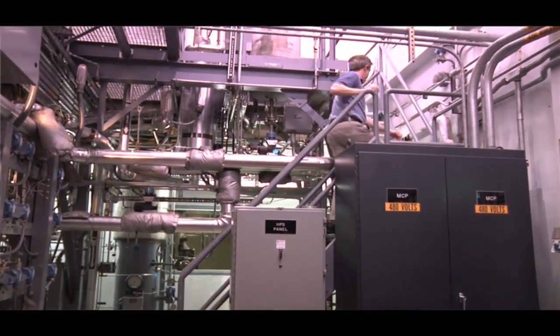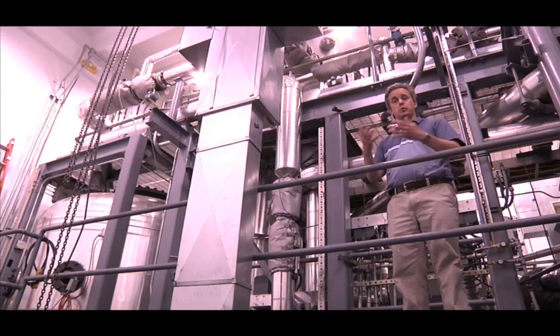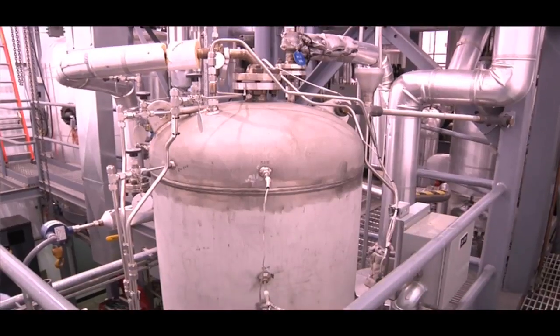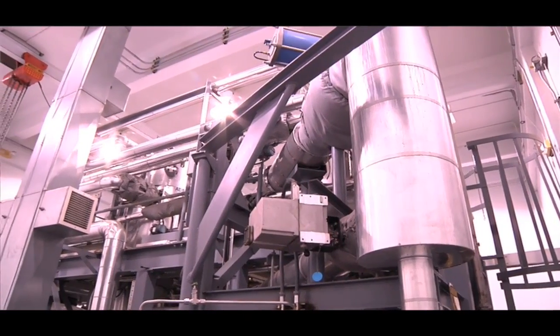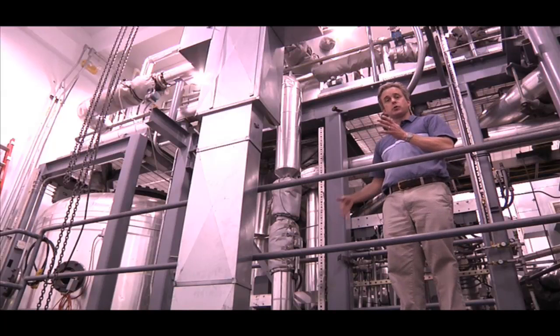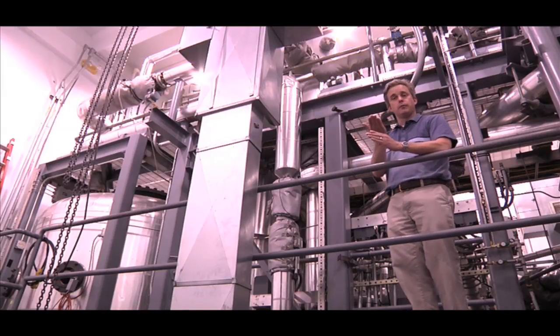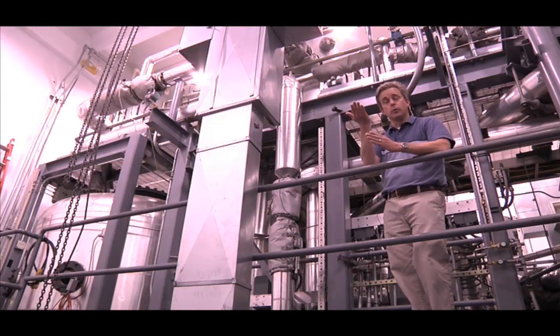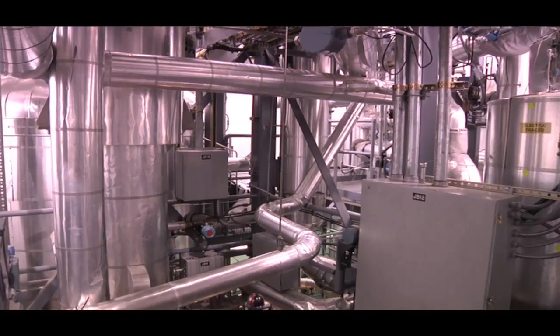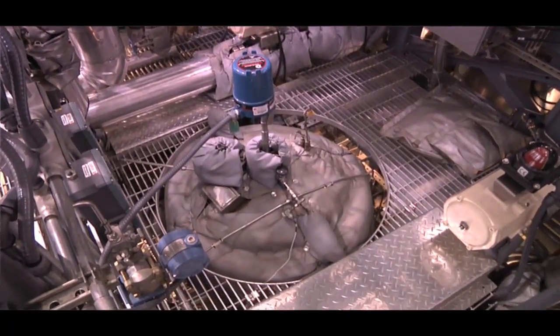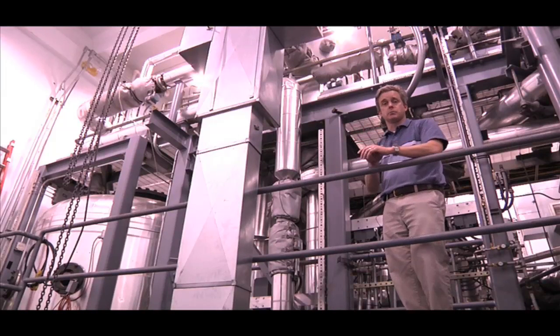The unique thing about this Advanced Plant 1000 is that it's what we call passively safe. If we were to have an accident in the sense that this reactor design had some sort of leak of the water that was to leave the reactor and the water levels start to drop, the number of tanks we have up here represents the passive safety features of this Advanced Plant 1000. And these tanks actually are filled with water as well. And as the water would drain out down in the reactor, which is below us because of some sort of leak, the water from these tanks here would then drain themselves into the reactor, which is below us, which then would be able to keep that water level above the radioactive fuel in the real reactor. And if the water level stays above the radioactive fuel in the real reactor, then you make sure in that case that the fuel doesn't melt. There's these kind of natural processes which actually are at play in this reactor design, which we're able to keep it in a safe condition during these different accident conditions, which makes it unique compared to the current generation of reactors and at the same time makes it much more safe as well.